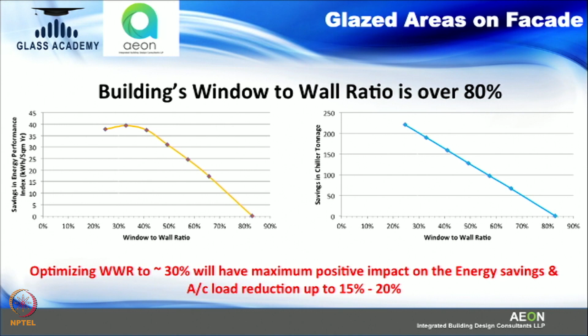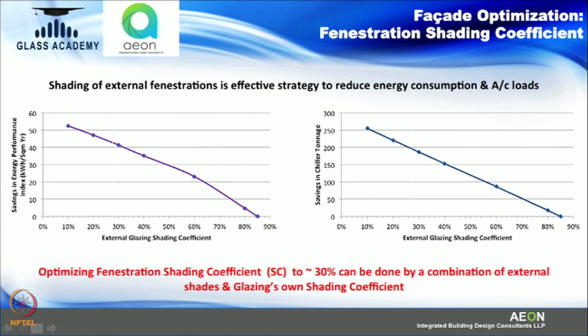This analysis is about fenestration's shading coefficient. How much shading coefficient should we go for? Again, the similar analysis on energy and chiller tonnage, and what was identified that a shading coefficient of 30% can be a good shading coefficient to look at in terms of optimizing the building performance. Then we did the daylight analysis to identify how much effect of different WWRs is going to be there on the daylight harness in the building.